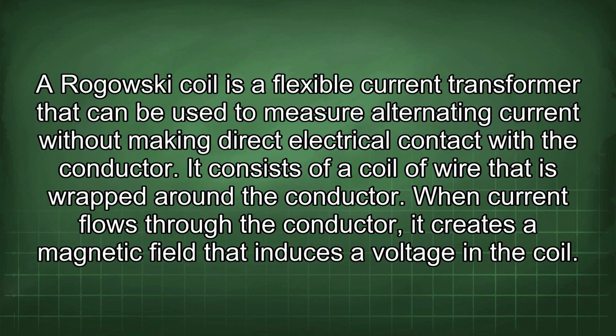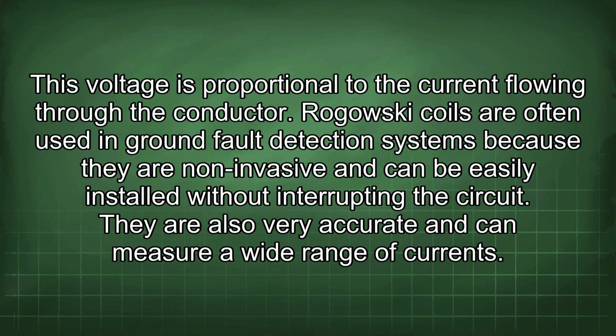A Rogowski coil is a flexible current transformer that can be used to measure alternating current without making direct electrical contact with the conductor. It consists of a coil of wire that is wrapped around the conductor. When current flows through the conductor, it creates a magnetic field that induces a voltage in the coil. This voltage is proportional to the current flowing through the conductor.